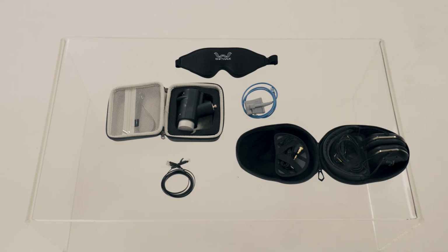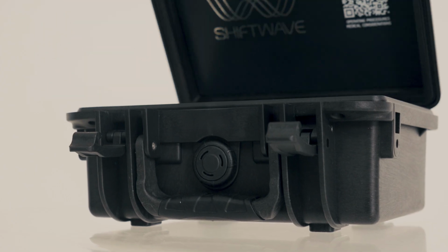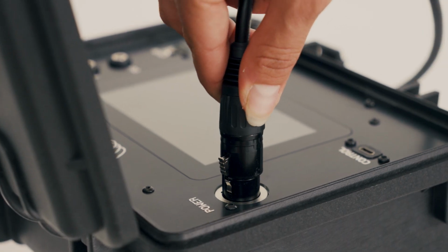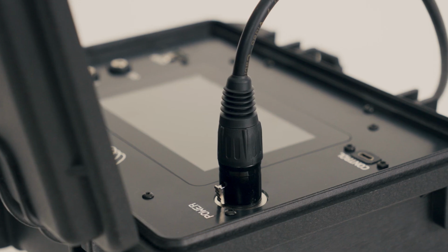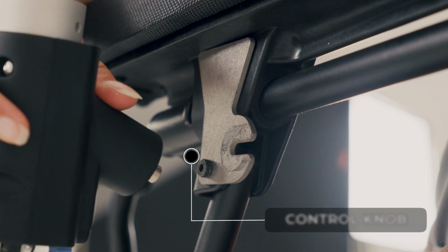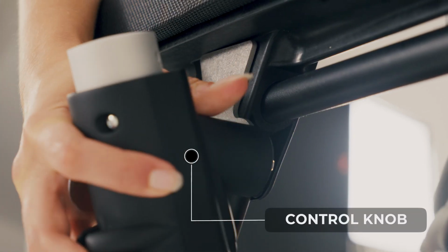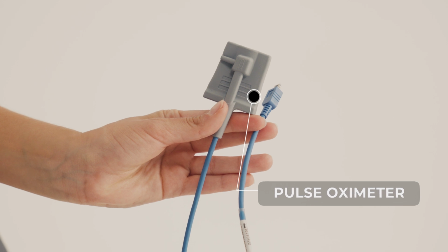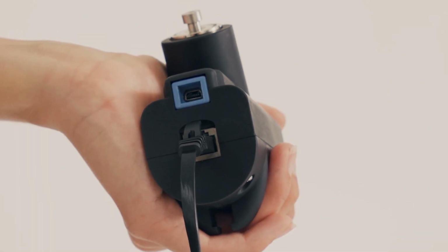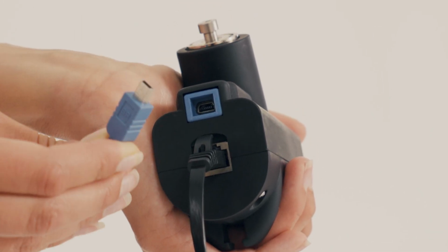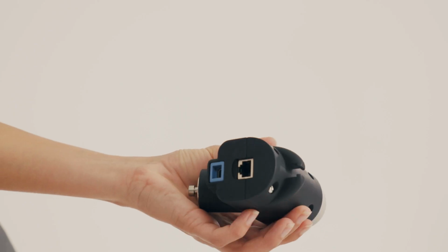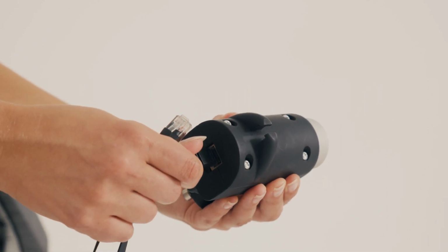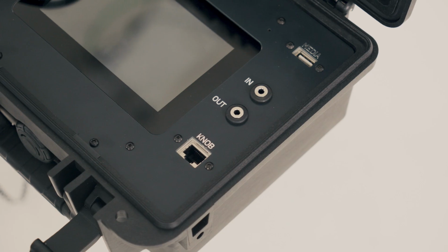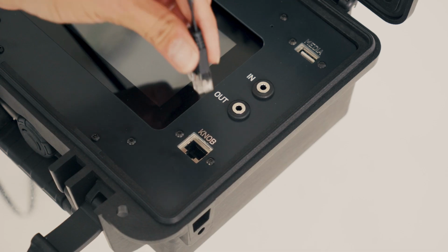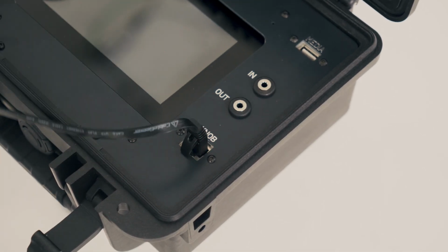Next, we connect the control box. Open up the control box and insert the power cable with the silver side facing up. Now attach the control knob and, if desired, connect the optional pulse oximeter. This part may take a few tries to align properly. Match the blue connectors. Then you plug the Ethernet cable into the bottom of the control knob. The other end of that cable gets plugged into the knob port in your control box.